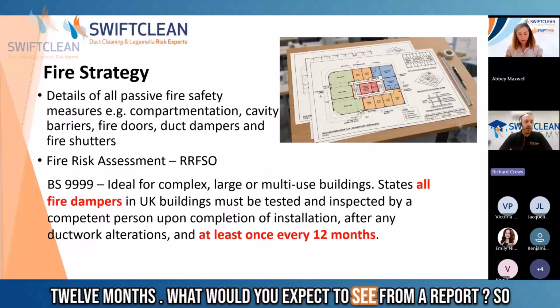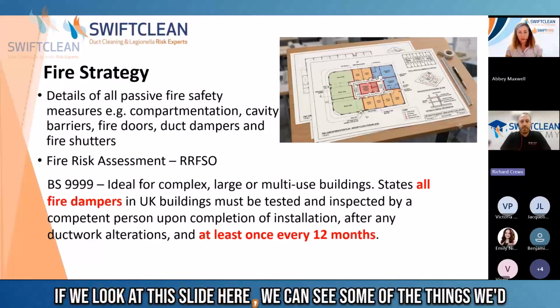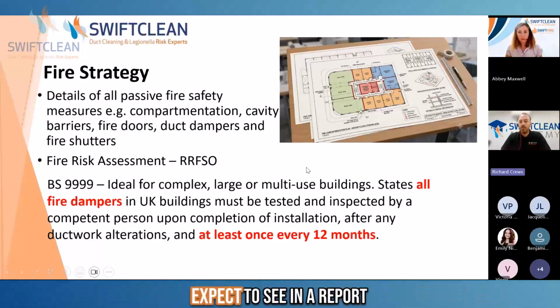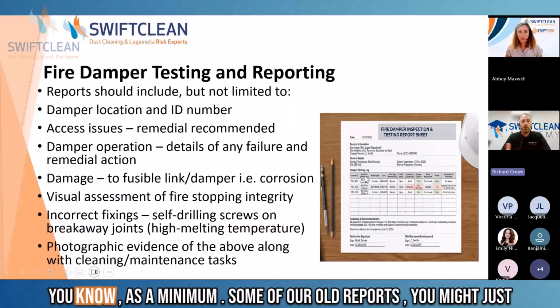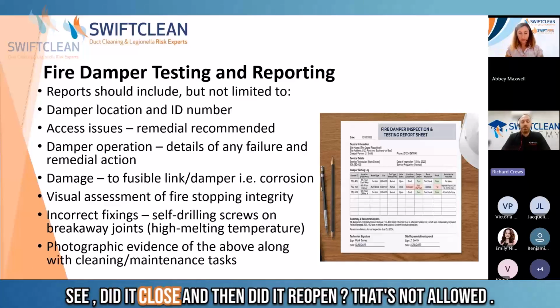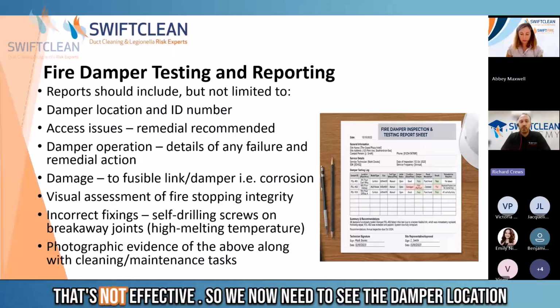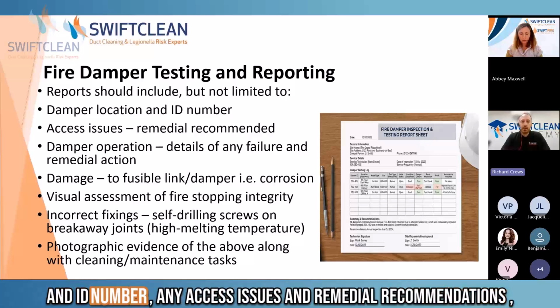What would you expect to see from a report? So if we look at this slide here, we can see some of the things we'd expect to see in a report as a minimum. Some of our old reports, you might just see, did it close and then did it reopen? That's not allowed. That's not effective. So we now need to see the damper location and ID number, any access issues and remedial recommendations.